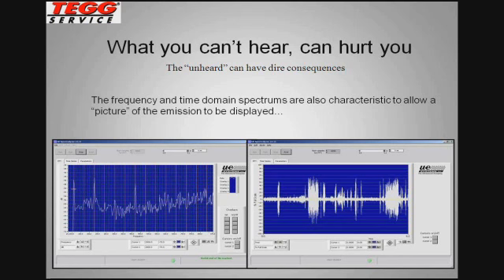On the right-hand side for the arcing, though, we see that band of noise through the middle all the way across the recording, but there are other elements imposed on top of that, and I call them excursions. Those are the points in time where the discharges are occurring. Moving left to right, we're silent for a portion, and then there's a discharge that goes to full intensity. Then it's totally quiet again, and we have several more discharges across the length of that 6 or 10 second recording. Explaining this in conjunction with the recording makes it far easier for a customer to understand. And when you compare this to samples that you know to be true, it's easy to make a good call. So those would be visualizing the arcing anomaly that we're talking about here.